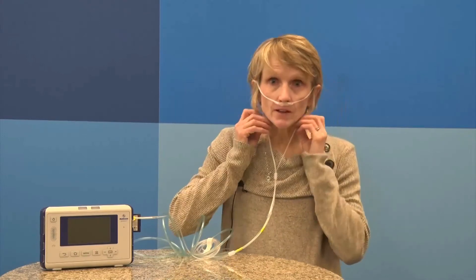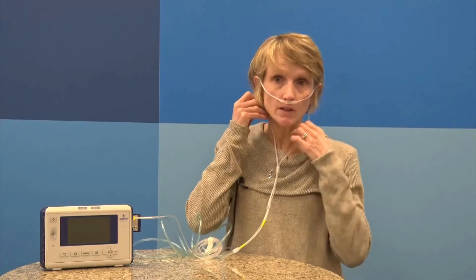Patients have reported discomfort at the tubing interface with the skin along the cheeks and ears, as well as an odor from the plasticizing material used to create the filter line. Lack of compliance with capnography monitoring can result in the inability to adequately assess the patient's respiratory status and hinder the clinician's ability to quickly detect and respond to changes in patient condition.